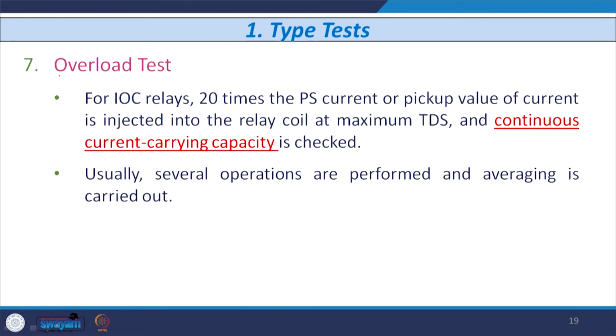The next type of test is known as the overloading test or overload test. This is also one of the type tests to be performed by the relay manufacturer. For all inverse time overcurrent relays, normally 20 times the plug setting current, or the pickup value, is injected into the relay coil with the maximum value of TDS. So, TDS is 1 in this case. And the continuous current carrying capacity of the coil or contact is to be checked.